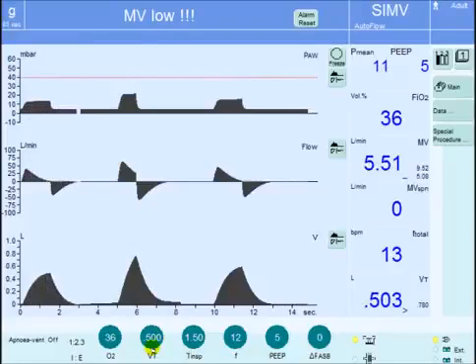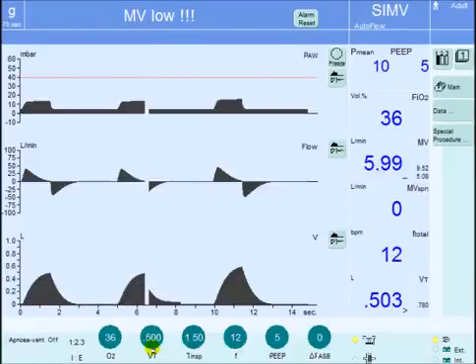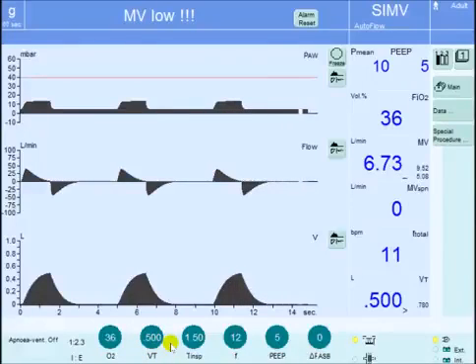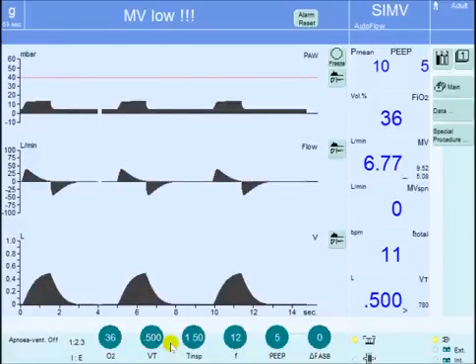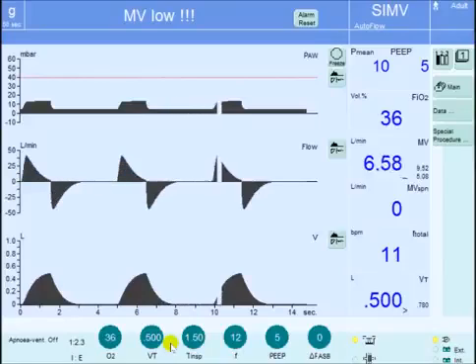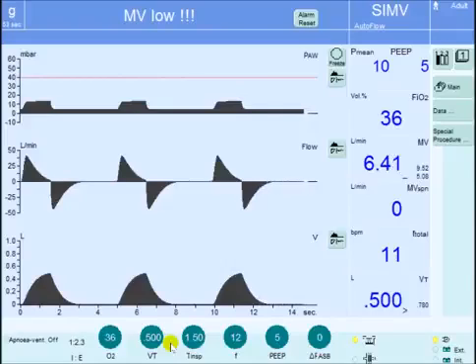In summary, pressure-regulated volume-controlled mode of ventilation, or Auto Flow on Draeger, is a mode that tries to achieve the target tidal volume with a minimum pressure. The change in pressure occurs gradually up or gradually down to achieve that target volume. I hope you benefited from this 5-minute critical care concept, and hope to see you in the next future sessions. Thank you.